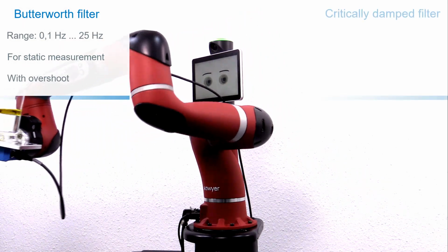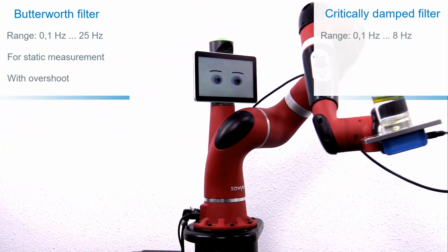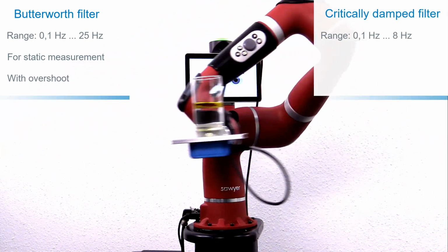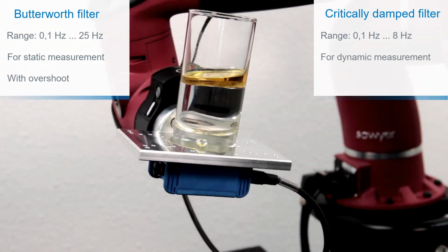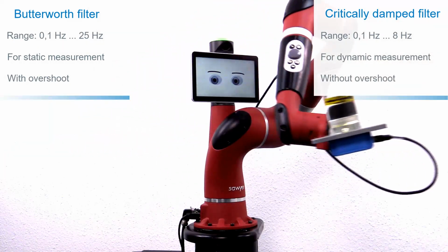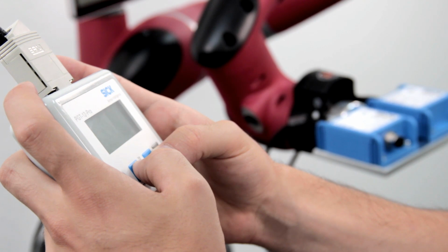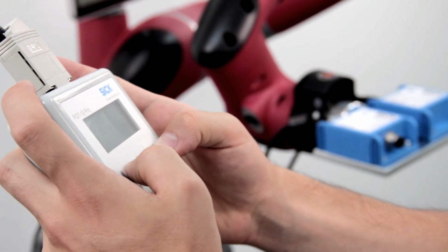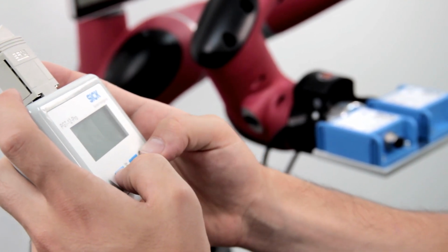The unique critically damped filter has a frequency range from 0.1 Hz to 8 Hz. This filter is used for dynamic measurements where no signal overshoot can be measured. Both filters can be parameterized via the PGT12 Pro handheld programming tool.